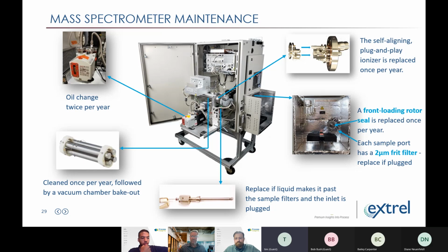Yeah, we normally keep common spares, and it is regulated to 5% or less per half for downtime. So we would certainly have the common spare parts on our shelf. Our contract customers, we look at the numbers, they maintain an uptime greater than 99% in these applications. Certainly, availability of on-site spares helps add confidence to that. Oh yeah, undoubtedly. My plant manager would give you a hug if you got 99%.